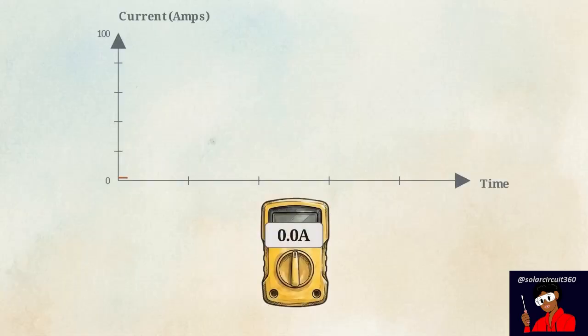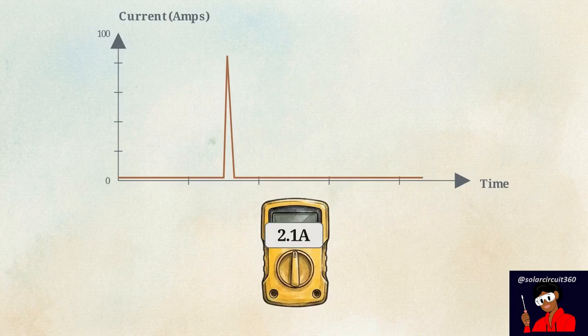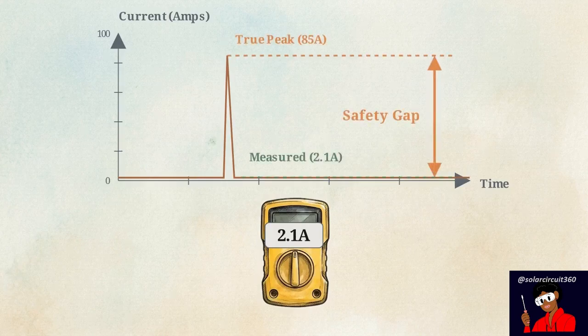These transient surge events happen so incredibly fast that if you measure the current with a standard digital multimeter, the screen will completely miss the true peak of the spike. Building your solar layout around the average running wattage guarantees failure during these peak transient events. You have to design for the surge dynamics.